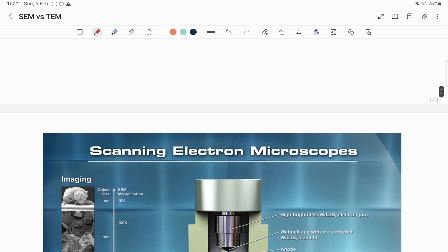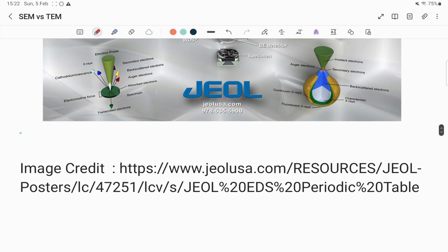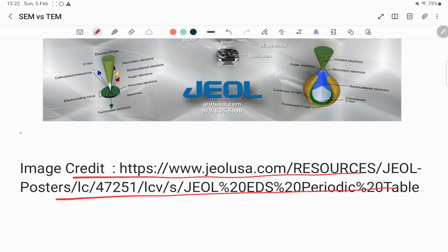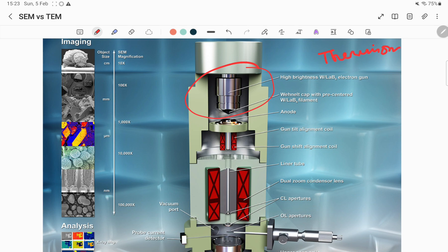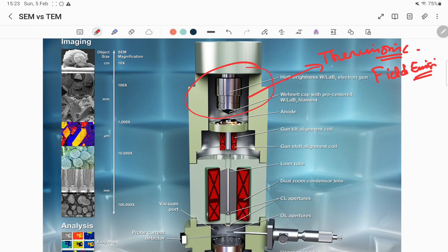Now we will see the schematics of SEM and TEM. This is the schematic of the scanning electron microscope — the image is taken from JEOL, and the source link is given here for more details. In SEM, the electron source can be thermionic or field emission type. For thermionic sources, tungsten and LaB6 are used as electron gun sources.